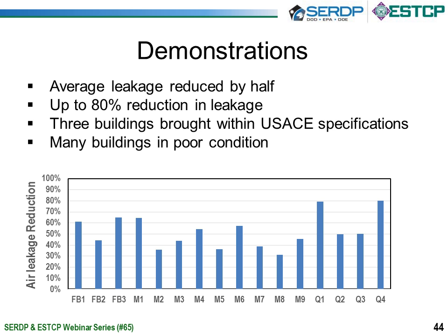3 of these buildings we were able to bring to within the USACE specification, which we were really encouraged by, considering many of these buildings were in poor condition. They were in some cases scheduled for demolition. So being able to bring some of those buildings to within spec and reduce the envelope leakage as much as we did, we were pretty happy with that.